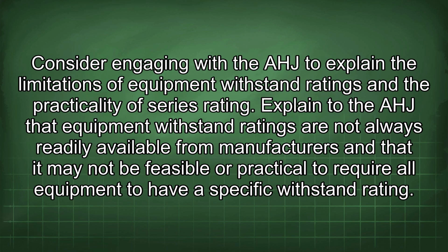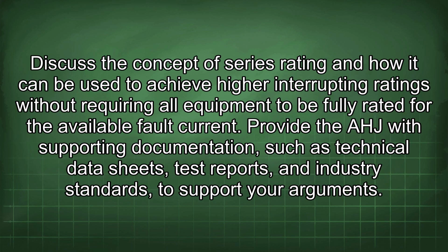Consider engaging with the AHJ to explain the limitations of equipment withstand ratings and the practicality of series rating. Explain to the AHJ that equipment withstand ratings are not always readily available from manufacturers and that it may not be feasible or practical to require all equipment to have a specific withstand rating. Discuss the concept of series rating and how it can be used to achieve higher interrupting ratings without requiring all equipment to be fully rated for the available fault current.